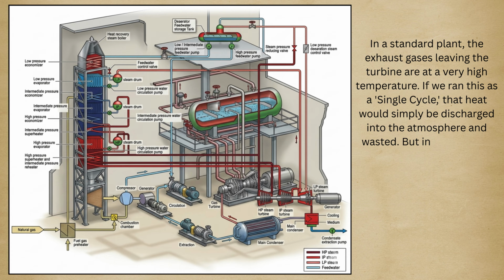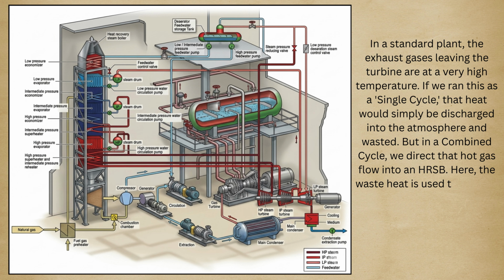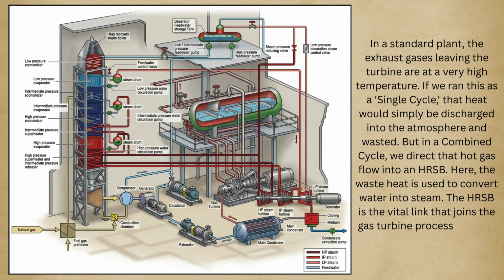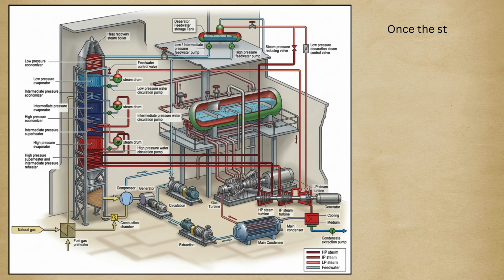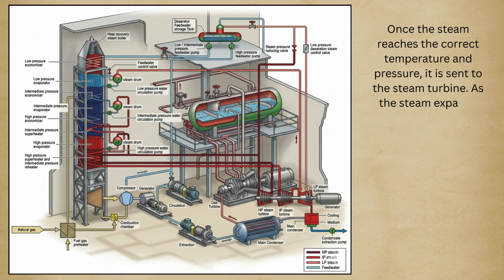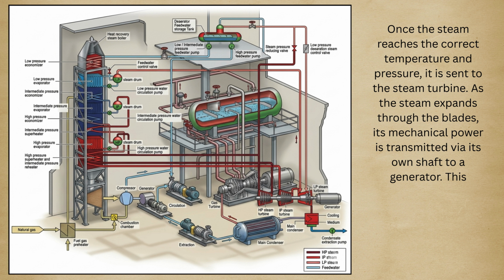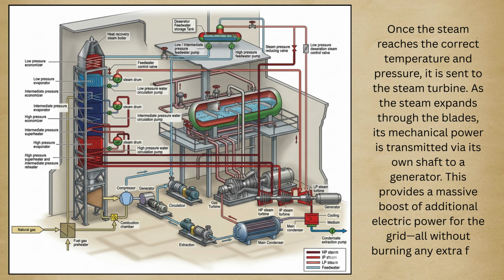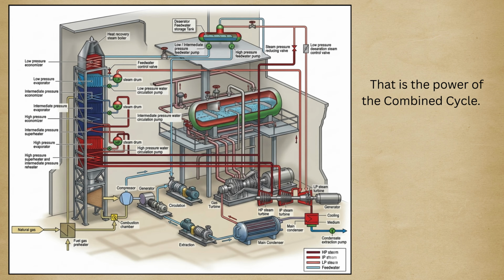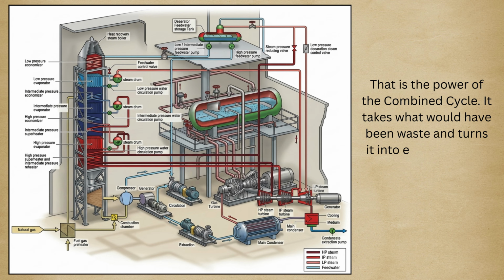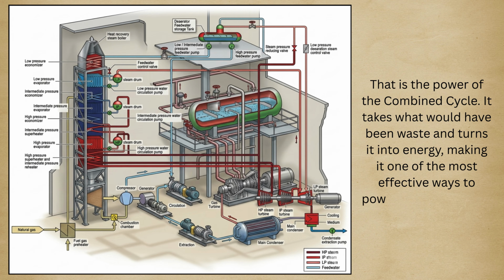But in a combined cycle, we direct that hot gas flow into an HRSG. Here, the waste heat is used to convert water into steam. The HRSG is the vital link that joins the gas turbine process with the water steam cycle. Once the steam reaches the correct temperature and pressure, it is sent to the steam turbine. As the steam expands through the blades, its mechanical power is transmitted via its own shaft to a generator. This provides a massive boost of additional electric power for the grid, all without burning any extra fuel. That is the power of the combined cycle. It takes what would have been waste and turns it into energy, making it one of the most effective ways to power our world today.